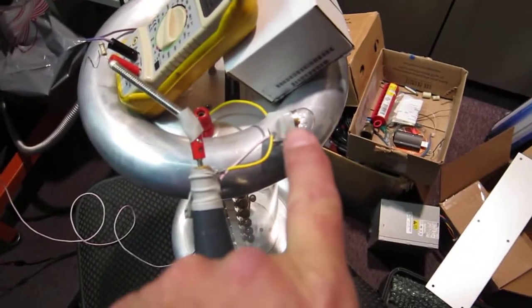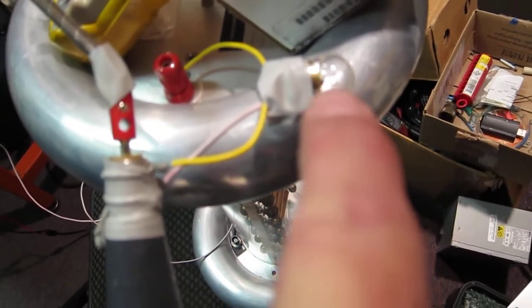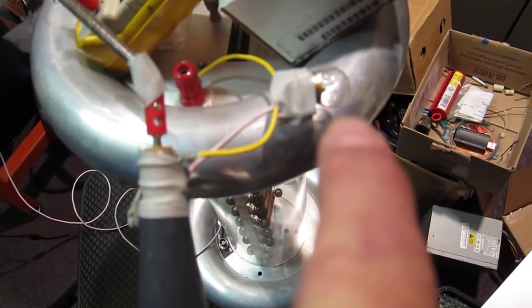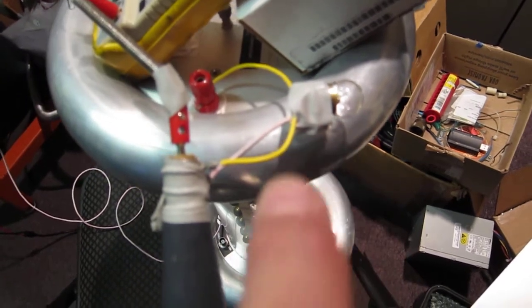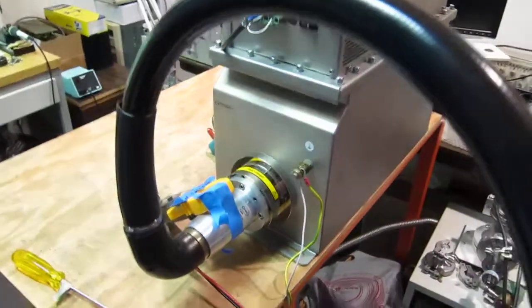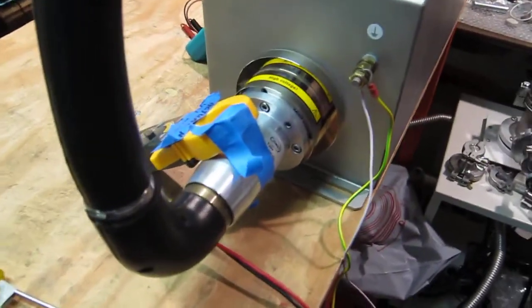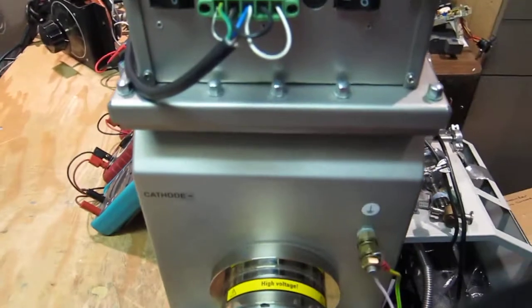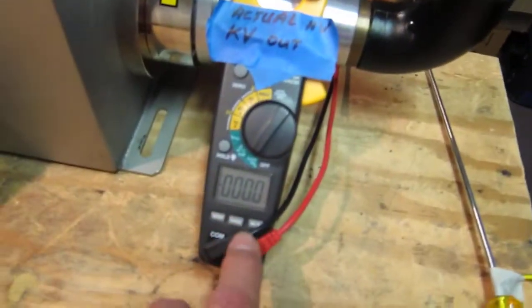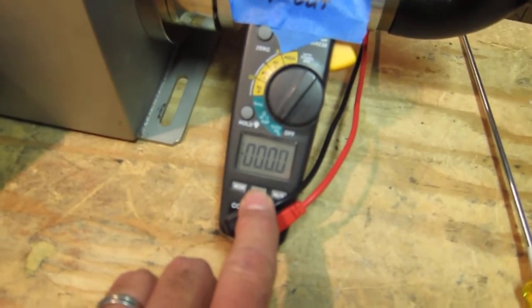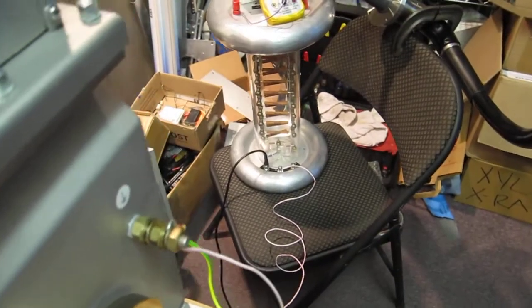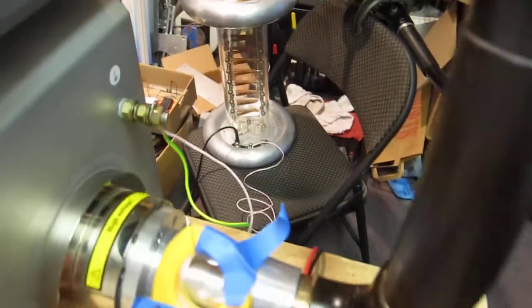Over here I have a small automotive light bulb to simulate the filament in the X-ray tube. And you can see this is the high voltage cone that would normally go into the X-ray tube, and the high voltage cable that's attached to the XRG-160. Also, this meter right here is reading the divided 1000 to 1 divided voltage from that large divider over there made by Glassman.